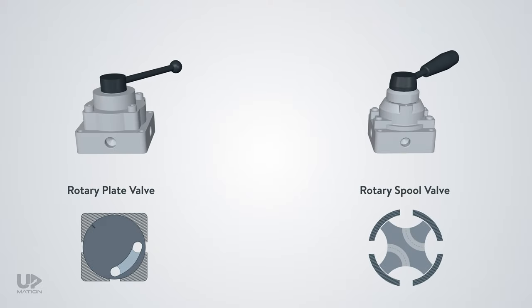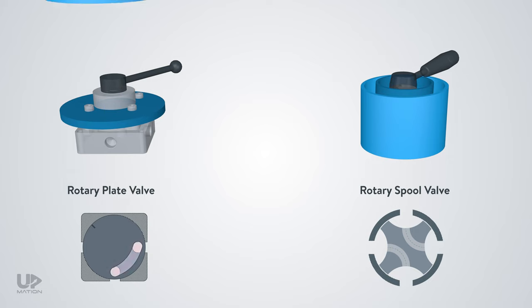Be aware to don't confuse this mechanism with a rotary spool valve. In the rotary spool valves, the holes in the spool and the ports on the housing will circumferentially match with each other, but in plate slide valves, the ports and the holes match with each other axially.